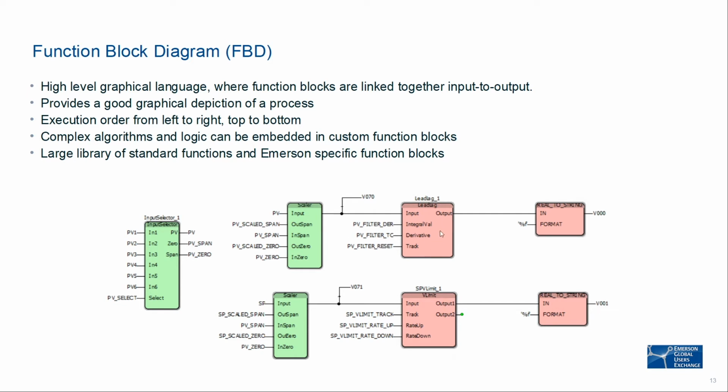And the red function blocks are firmware function blocks, while the green function blocks here are actually custom function blocks, where if you click on that custom function block, you can write what happens in that function block, and you can write that in any language you want. You can have a custom function block that consists of structured text or instruction list or even more function block diagram, and then put that in your diagram. You can also make these custom function blocks and put them in structured text, and it would just appear as an extra line that says the name of your function.